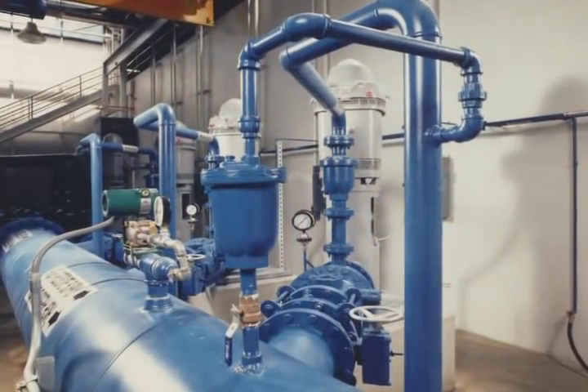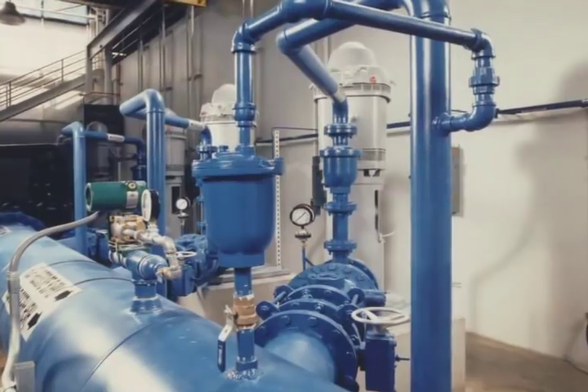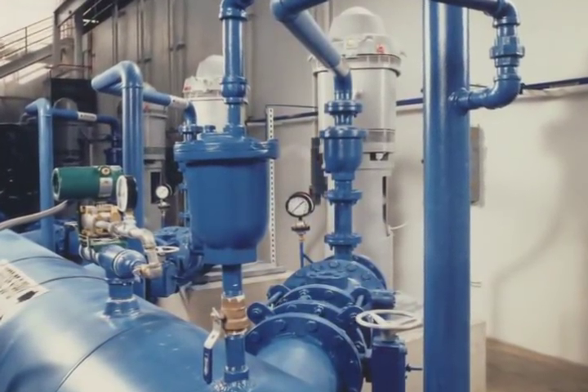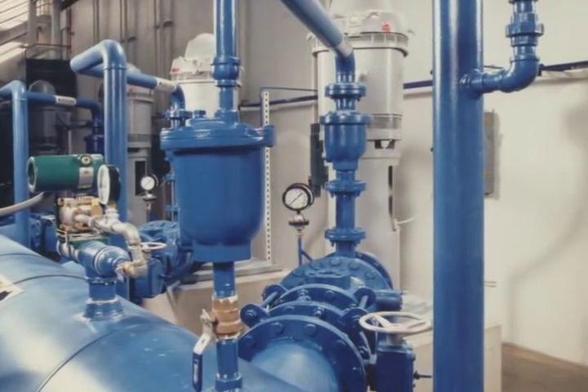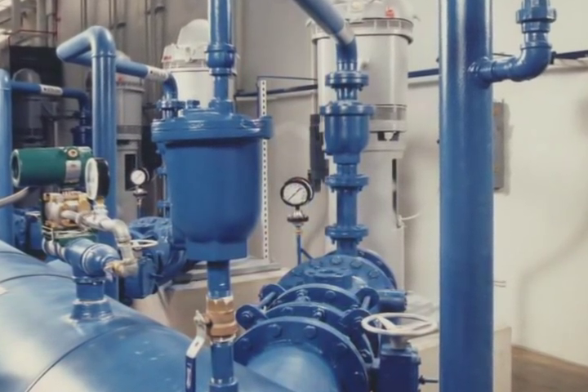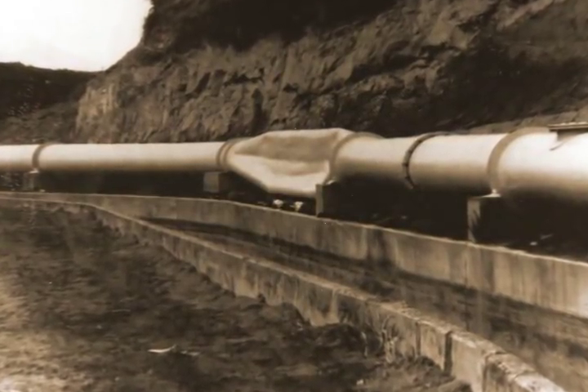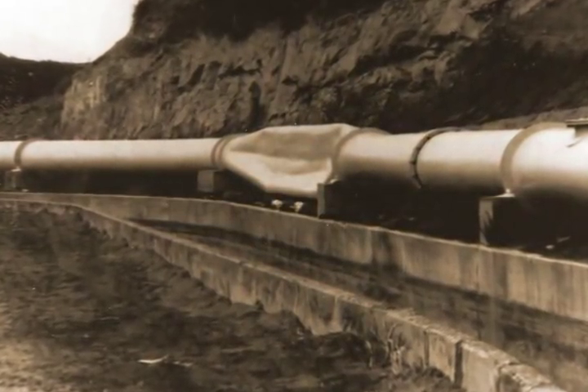In reality, many of these problems are not caused by improper installation of the line, but by failure to de-aerate the line. Properly de-aerating your pipeline will safeguard it from air-related problems. If this isn't accomplished or is done improperly, efficiency will suffer and the pipeline is at risk.